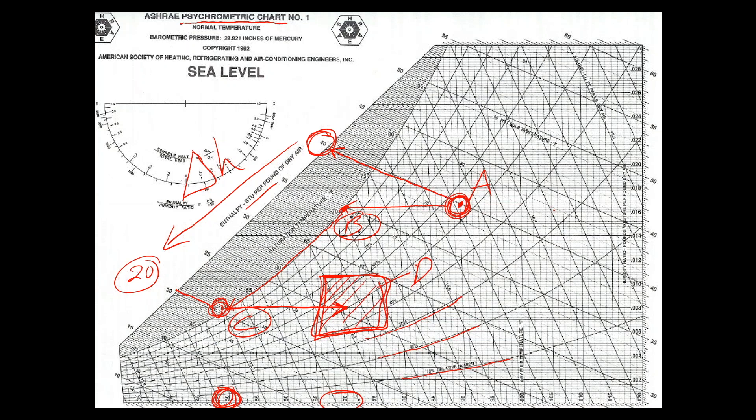Now, let's erase the zone here just to show you the real deal here. So, if we were to reheat this air back to, say, I don't know, like I said, 70 degrees, we would come along this line to the point of 70. Okay. And, the enthalpy in this final condition would be we would have to go on this line like this. And, again, we're just kind of estimating where this would hit. And, it's not perfect, but pretty close to 25.